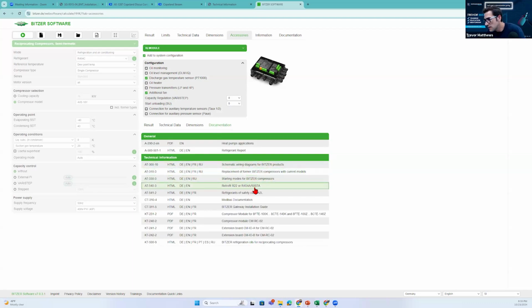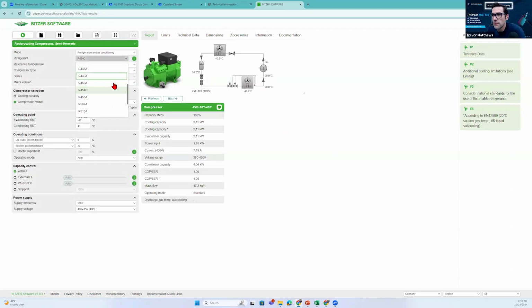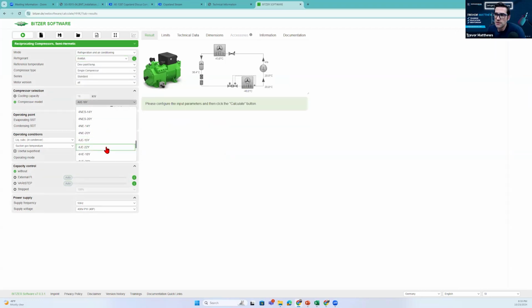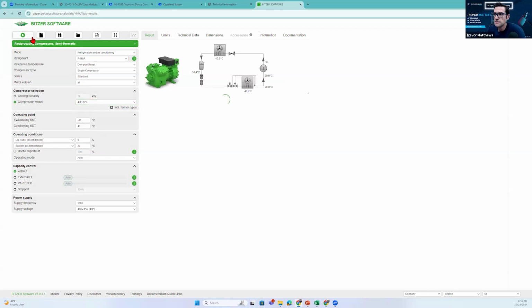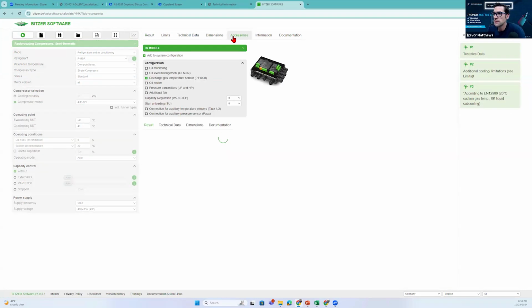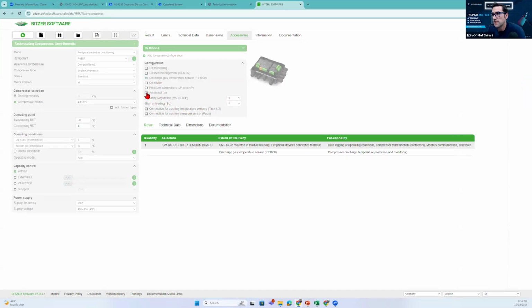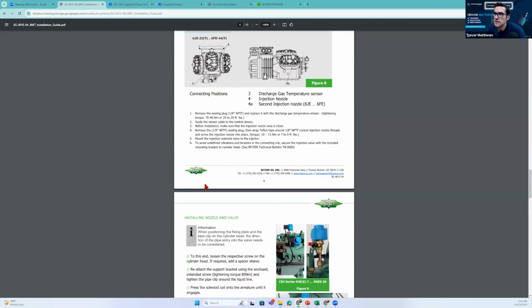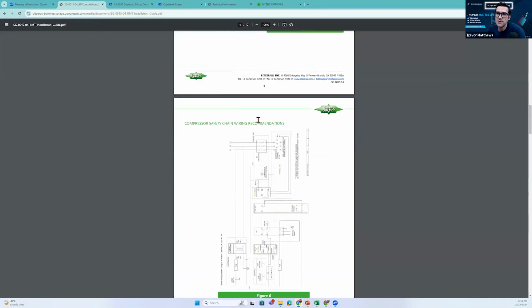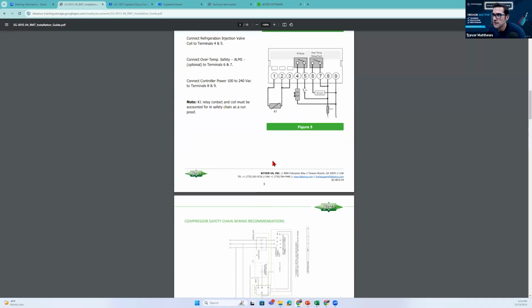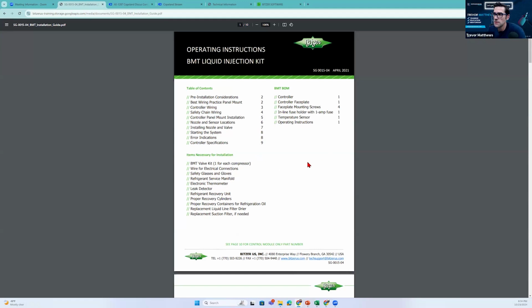Sometimes you would see, down here, it doesn't have the manual. Usually it'll have the manual for, which one did I do earlier tonight? Let's just check that out. Let's go to 448, 449, I think it was. Maybe it's a different compressor too, because different compressors will yield different results. Once again, accessories. And all these will just need an additional fan, which is great. Okay, I found the technical document. So this is the technical document. All I did was search Bitzer refrigerant injection module, and it's the BMT liquid injection module.